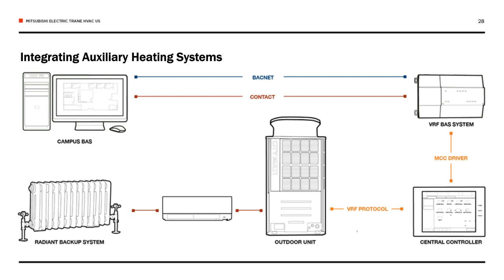Then we get into scenarios where they want it integrated a certain way, or to only work below a certain temperature, or to only enable when the outdoor unit is completely maxed out, or to only enable when the temperature offset from the desired temperature to the actual temperature in a room is X. So that's a lot of different scenarios of how a customer or designer wants that auxiliary heat to work. In that situation, you might need something like what's on the screen here, with advanced programming and sequencing to accomplish all that and make it happen.